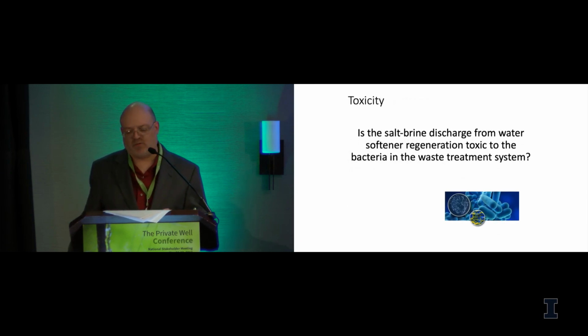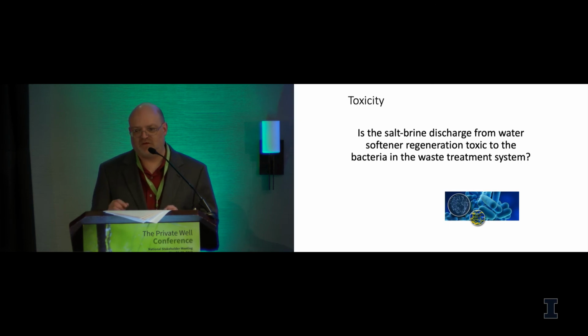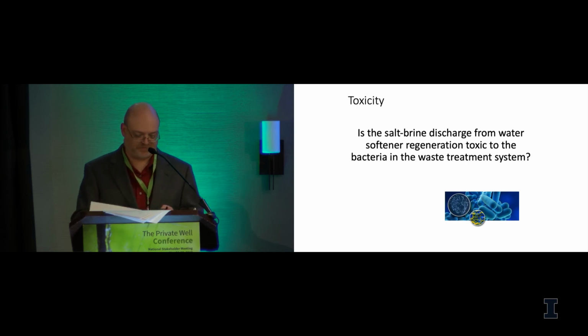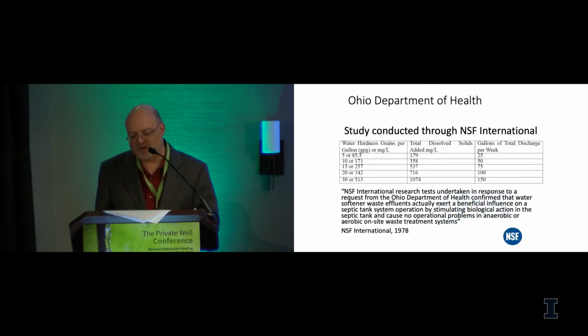So the next topic I want to talk about is toxicity. And this gets down to, we need to understand, is the salt brine discharged from water softener regeneration toxic to the bacteria in the waste treatment system? So again, this was looked at by NSF International. This table here shows the conditions that they studied. They looked at various levels of hardness from 5 grains to 30 grains, so some pretty hard water, various levels of TDS, and they also looked at various levels of discharge, up to 150 gallons of discharge.